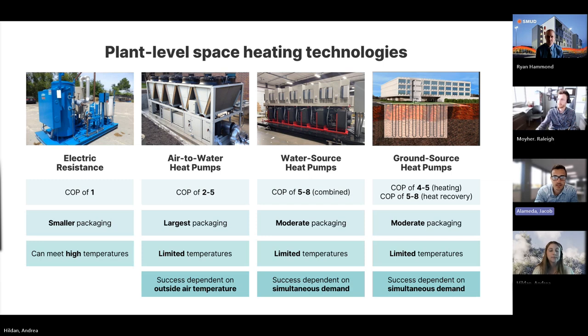So looking at the screen and moving left to right, each one of these equipment types goes up in efficiency as you move to the right. The first equipment type on the left is an electric boiler, and that's kind of exactly what it seems like.